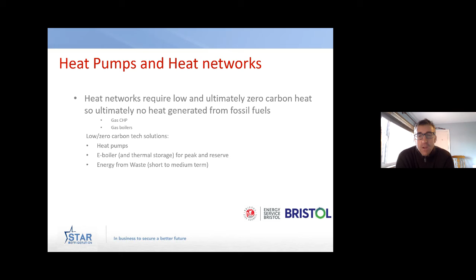For us, the big thing about heat networks is that we can install the heat pipe work, but it's the development of the heat pump energy centres on the end of those pipes that's probably the trickiest bit, especially for cities, installing heat networks and energy centres in already built-up city centres with tall buildings and planned new ones. So the main thing is to utilise HNDU funding if available, or apply for it, to really look at the energy centre options and solutions open to you, because the key issues are around the resource opportunity.